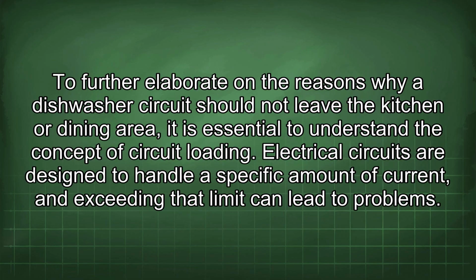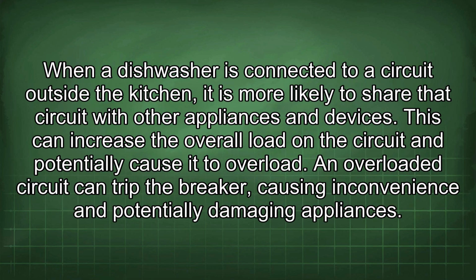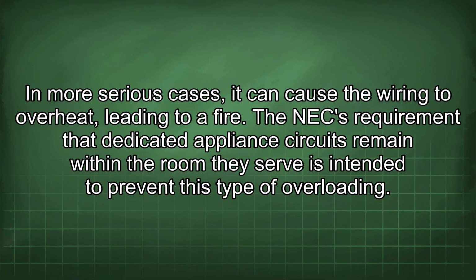To further elaborate on the reasons why a dishwasher circuit should not leave the kitchen or dining area, it is essential to understand the concept of circuit loading. Electrical circuits are designed to handle a specific amount of current, and exceeding that limit can lead to problems. When a dishwasher is connected to a circuit outside the kitchen, it is more likely to share the circuit with other appliances and devices. This can increase the overall load on the circuit and potentially cause it to overload. An overloaded circuit can trip the breaker, causing inconvenience and potentially damaging appliances. In more serious cases, it can cause the wiring to overheat, leading to a fire. The NEC requirement that dedicated appliance circuits remain within the room they serve is intended to prevent this type of overloading.